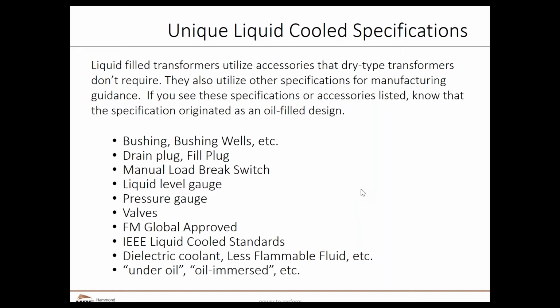Valves. FM Global Approved is an insurance agency that does a lot of work with commercial properties, especially in North America. They tend to have certain specifications for liquid filled transformers. So having something that might meet their overall specifications will help standardize what the insurance policy is for that area. We will see certain IEEE standards that are specific to liquid filled versus dry type. Again, we might see things like dielectric coolant, less flammable fluid, under oil or oil immersed. All of these terms and conditions are really reflective of a liquid filled transformer.